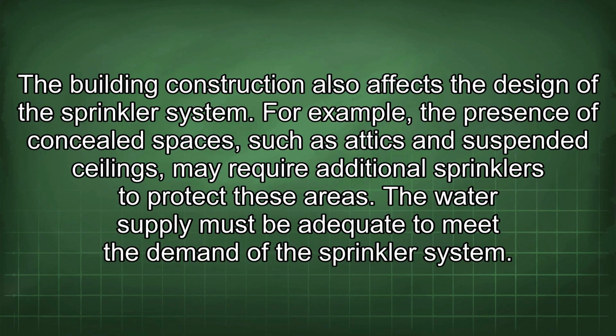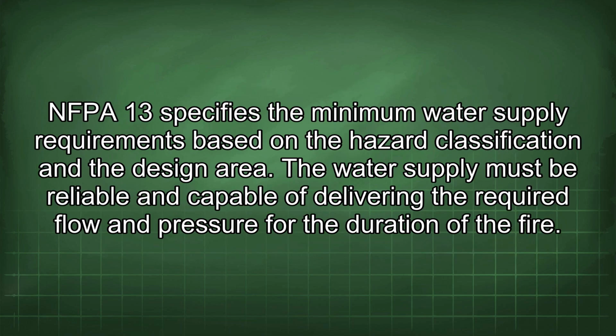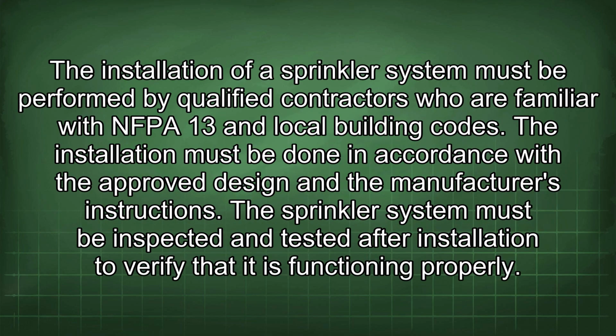The building construction also affects the design of the sprinkler system. For example, the presence of concealed spaces, such as attics and suspended ceilings, may require additional sprinklers to protect these areas. The water supply must be adequate to meet the demand of the sprinkler system. NFPA 13 specifies the minimum water supply requirements based on the hazard classification and the design area. The water supply must be reliable and capable of delivering the required flow and pressure for the duration of the fire. The installation of a sprinkler system must be performed by qualified contractors who are familiar with NFPA 13 and local building codes. The installation must be done in accordance with the approved design and the manufacturer's instructions. The sprinkler system must be inspected and tested after installation to verify that it is functioning properly.